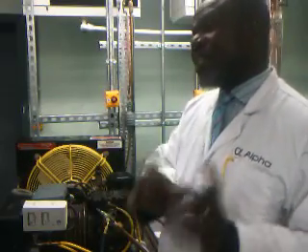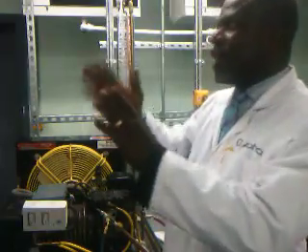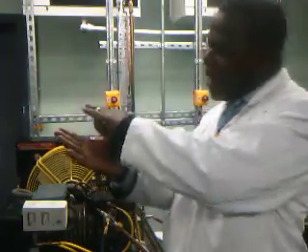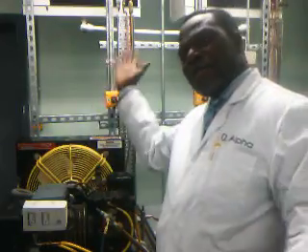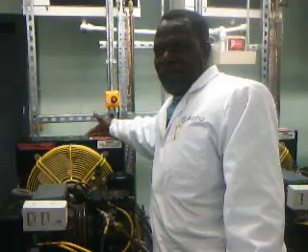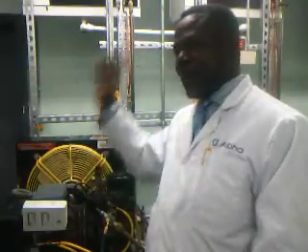But before you charge the system up, check the fins. Are your fins straight, with no bends blocking the airflow? Is there anything blocking the airflow? Check that as well, and check whether the condenser is dirty. It's got fouling, papers, rubbish sticking on it and blocking the airflow. You have to check all that.